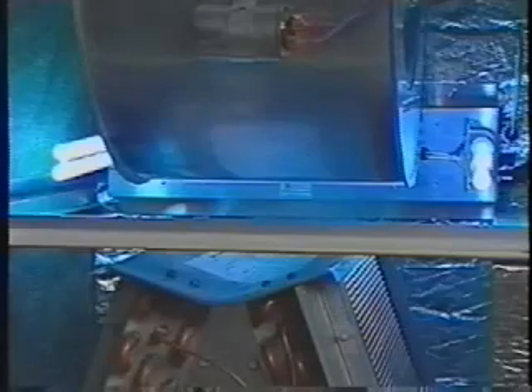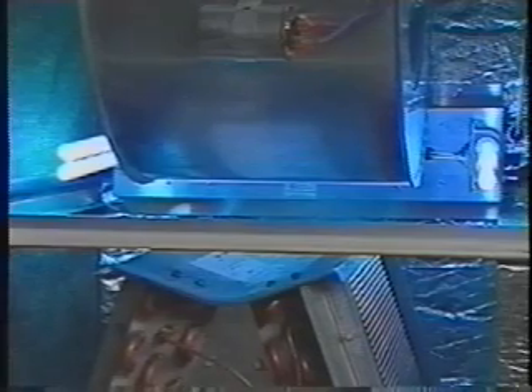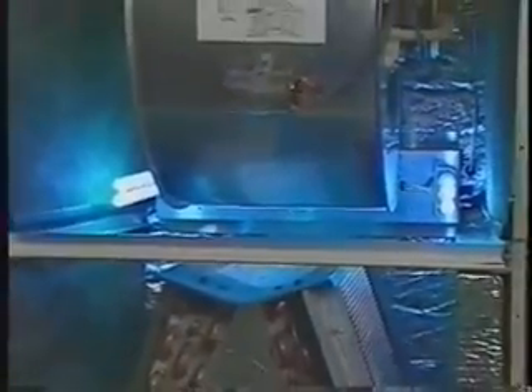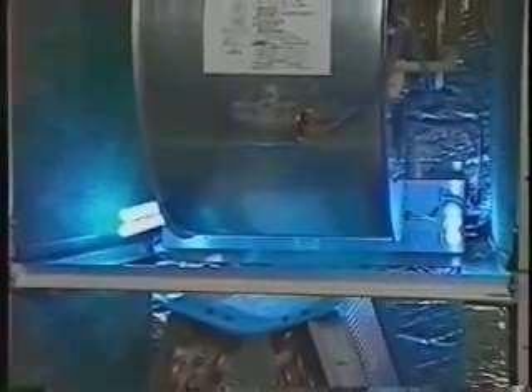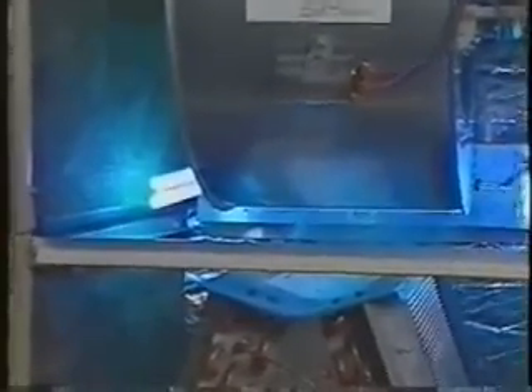Another point we would like to make on an installation such as this: due to the fact that there is so much space between the bottom of the fan and the top of the evaporator coil, this unit can actually be slid back underneath and affixed on the back wall without ever having to remove the fan. That makes this installation a whole lot easier.